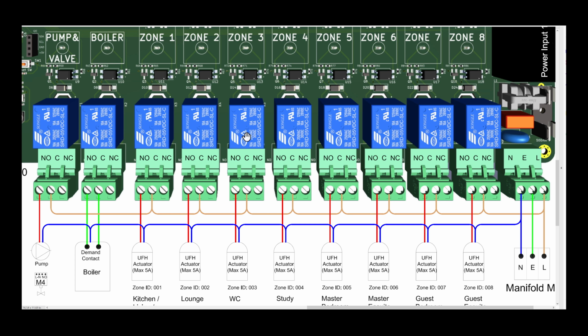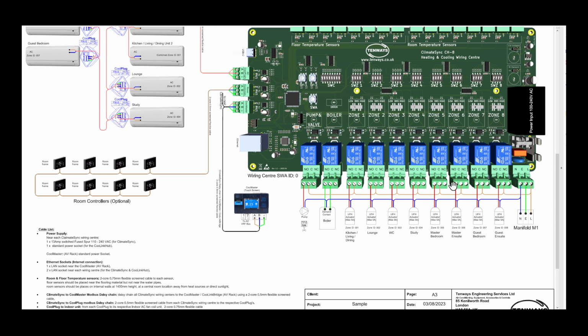Where you have electric underfloor heating on some zones, you will set a dip switch on the controller, on the board, and therefore that zone will not activate the boiler and the pump. In cases where we have radiators, you will also set that up, and then it will start the boiler but will not start the pump. If you have a zone set as I/O only, on and off only, without temperature control, then you will set up the setup so that specific zone does not activate the boiler and the pump. So these are the bottom connections.